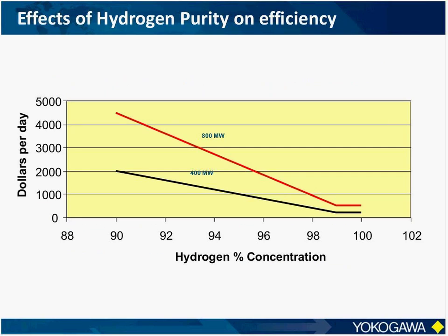As the hydrogen purity decreases, you see that thousands of dollars are lost due to the decrease in efficiency. This is because that rotational energy is being transformed into a heat energy friction rather than electrical energy. And you can also see that this effect is multiplied as the capacity of the generator increases.